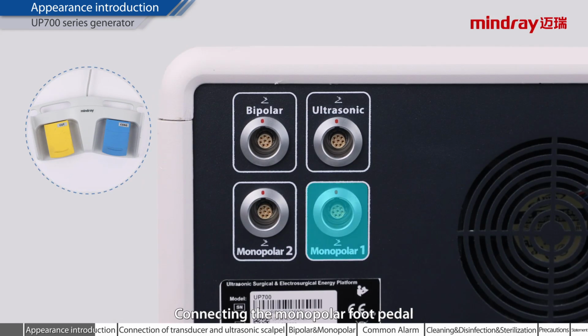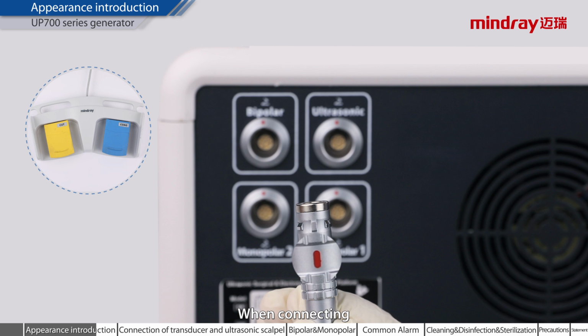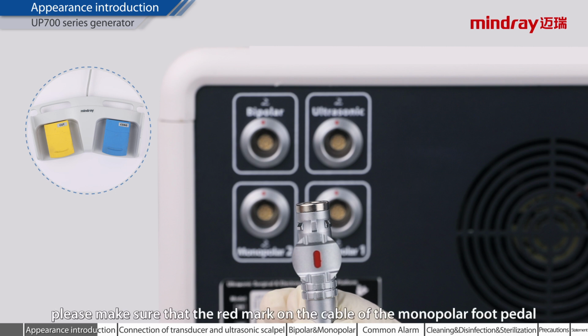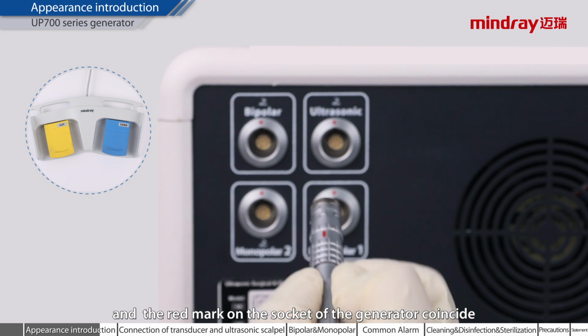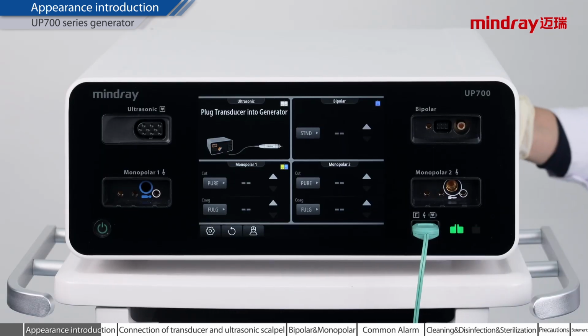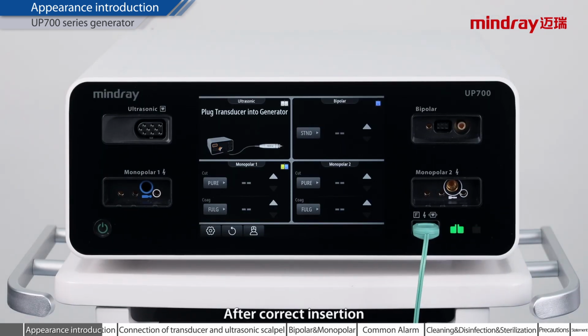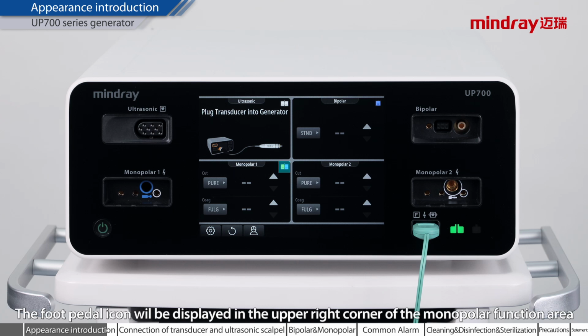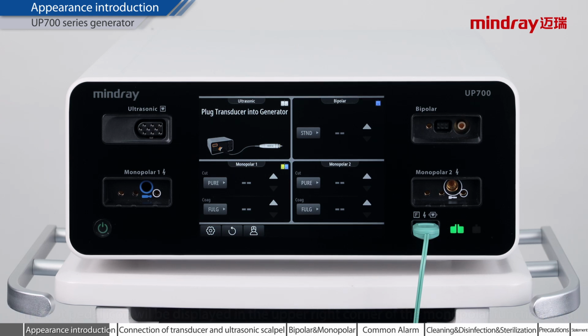Connecting the monopolar foot pedal. When connecting, please make sure that the red mark on the cable of the monopolar foot pedal and the red mark on the socket of the generator coincide. After correct insertion, the monopolar function area displays that the foot switch has been plugged into the monopolar sockets. The foot pedal icon will be displayed in the upper right corner of the monopolar function area.